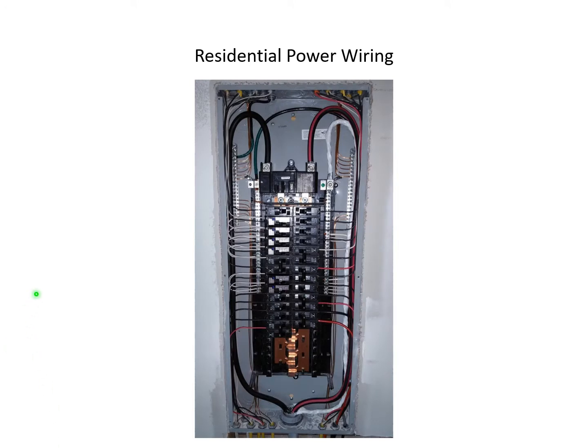Now, this is a picture of a typical residential power system. In this case, the main power is coming in from the bottom and comes up here to the top. And here's one leg of the main power. And here's the other leg coming in and feeding here. And so what you have from here to here is 240 volts. And then there's a bar that runs through the panel all the way down on this side that carries this side's voltage, and then a similar bar on the other side, and then neutrals in the center.